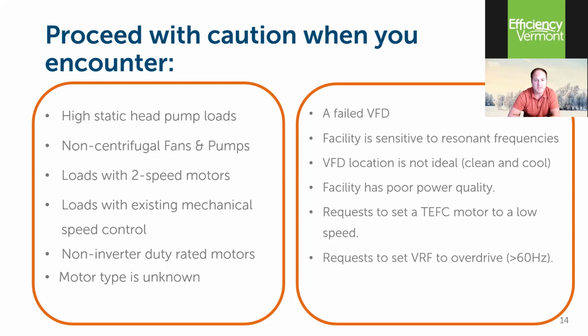Facility is sensitive to resonant frequencies. So this is an electronic device. It creates harmonics. There are filtering devices that can limit that. If that's important to your customer, your facility, I encourage you to speak with your VFD supplier about harmonics and what they can do to mitigate that. Do that up front so that you're not surprised by it after, when the drive goes in, that it's actually part of the implementation process.